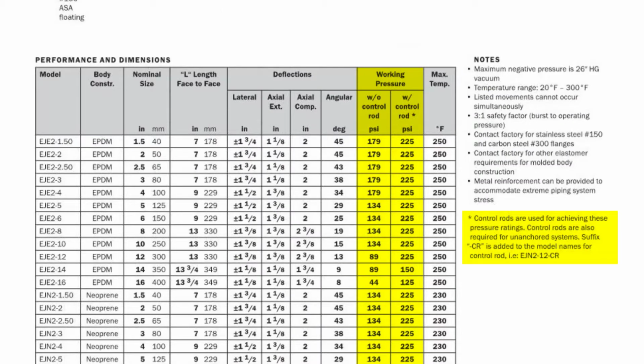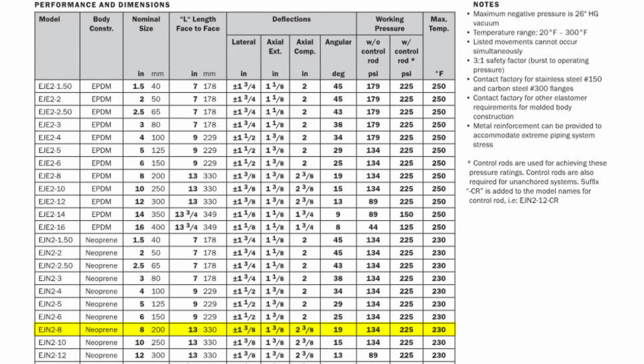The next columns show us the maximum working pressure with and without control rods, which are used to achieve higher pressure ratings or where needed to prevent excessive movement. And the last column shows the maximum temperature of fluid flowing through the joint. These temperatures are above what is commonly found in HVAC systems. Note that EPDM is suitable for slightly higher temperatures than neoprene. It is also more suitable for use outdoors where exposed to ultraviolet rays. The expansion joint we just looked at was an 8-inch diameter neoprene model, so we'll want to keep in mind the various dimensions and operating limitations listed here during our review.